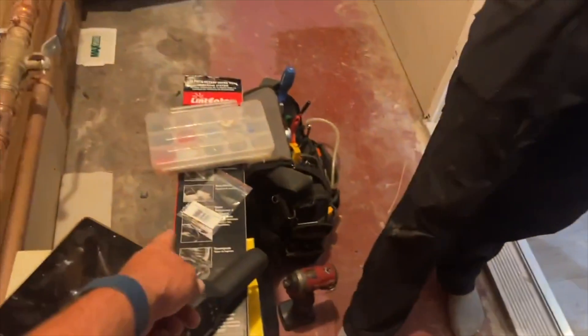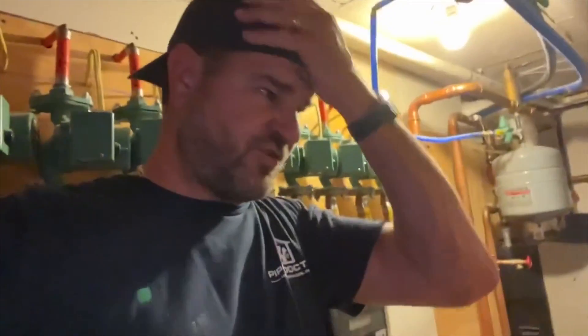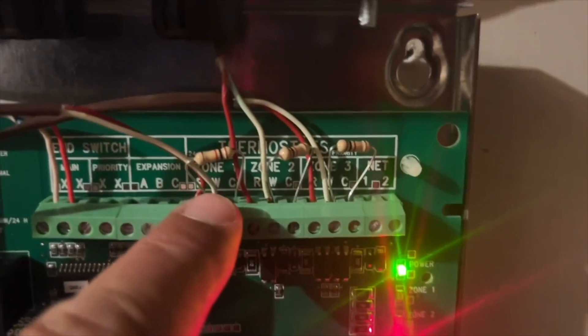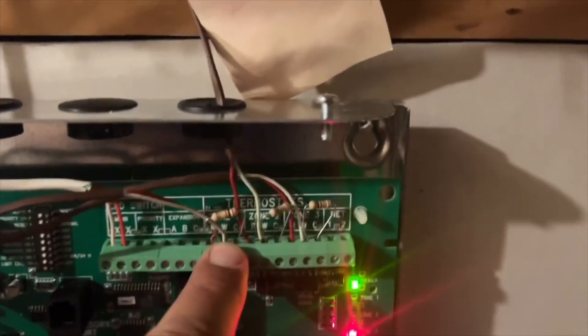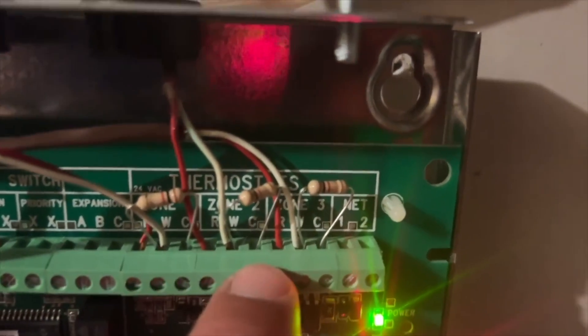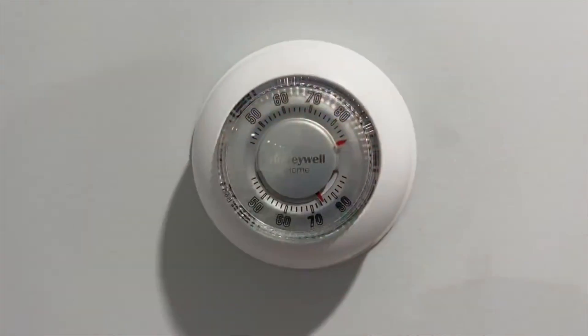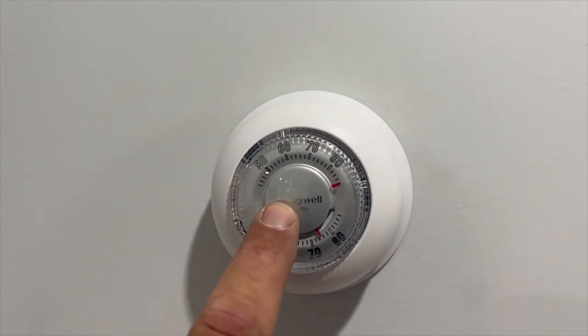Honeywell supplies those resistors. We're going to take them and put them across WC on all these zones. Let me show you what I did here at the Taco SR-503 switching relay. As you can see, I have these little half-watt, 1,000-ohm resistors that came with the Taco SR-503. I have one on zone one between W and C, zone two between W and C, and zone three between W and C. We're installing these because this is a power-stealing thermostat — it steals power from the relay in order to function.